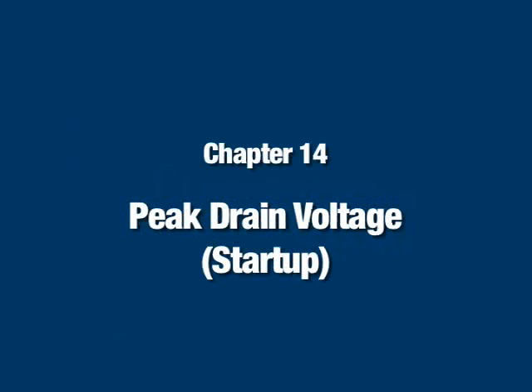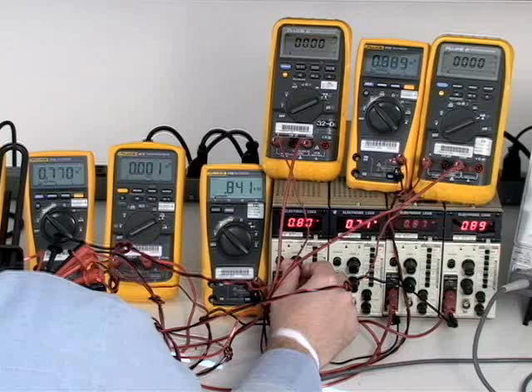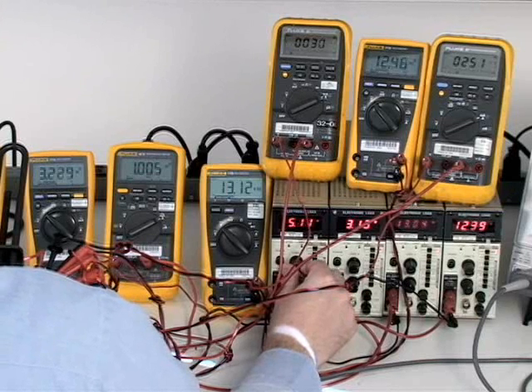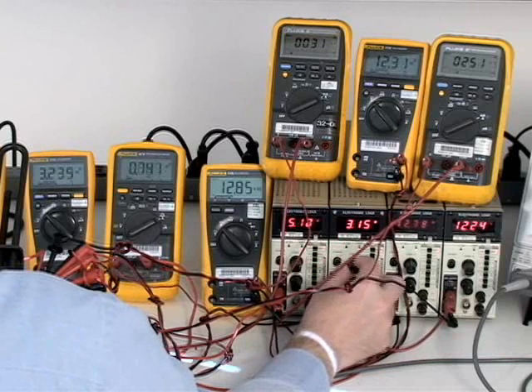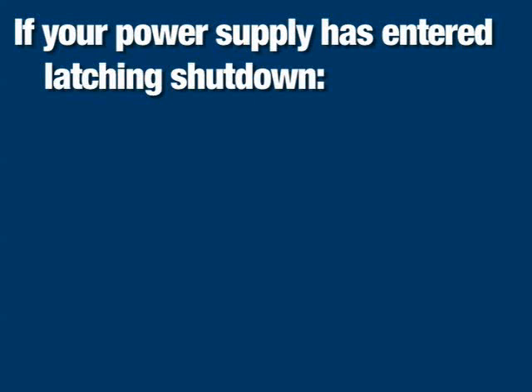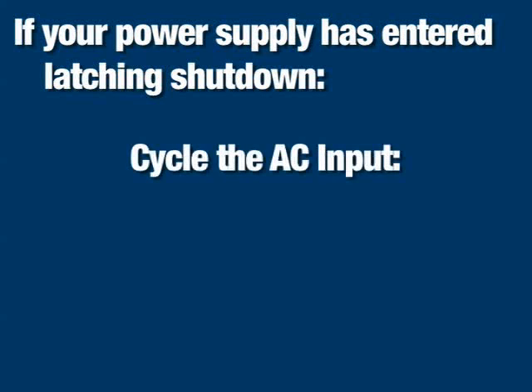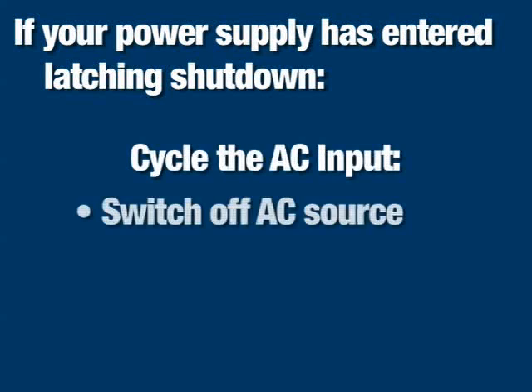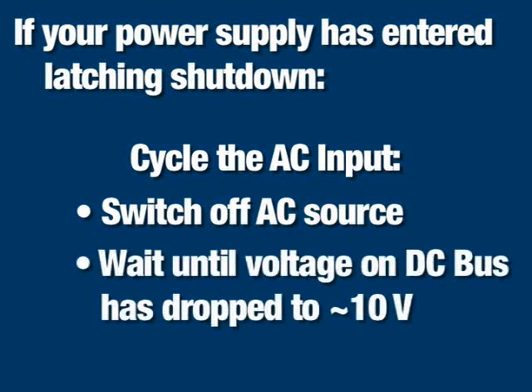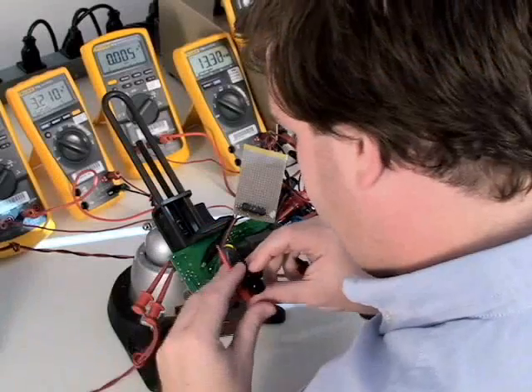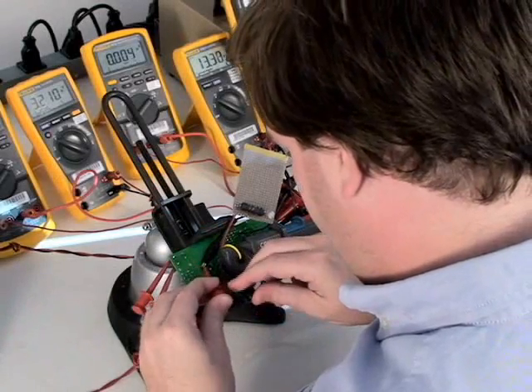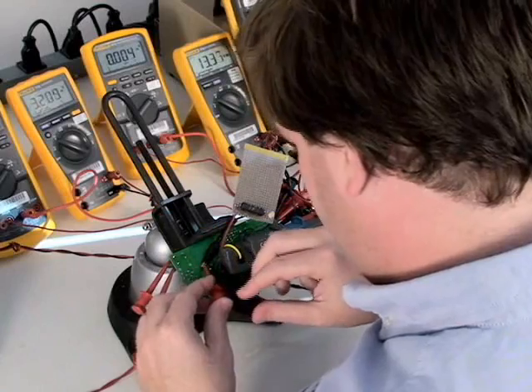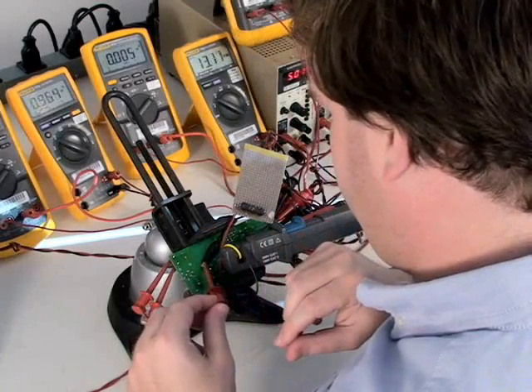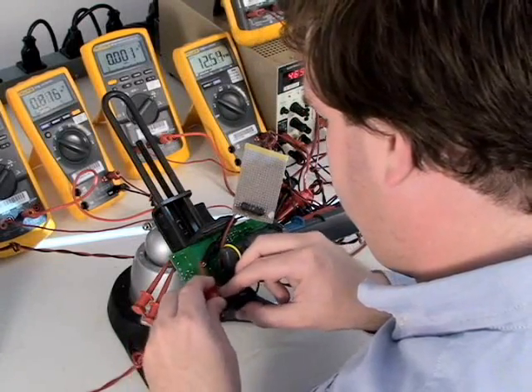Chapter 14. Peak Drain Voltage Startup. For the next test, reduce the load on the supply back to full load. If your power supply has entered latching shutdown, it may be necessary to cycle the AC input before the supply will return to normal operation. Switch off the AC source and wait until the voltage on the DC bus has dropped to about 10 volts. If a large value bulk capacitor is used in your design, this may take several minutes. The process can be accelerated using your capacitor discharge board.